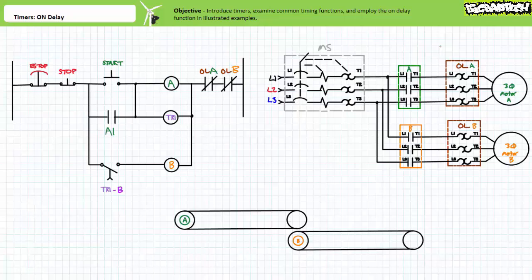That is that for this lecture. I was going to dive into on-delay timers coordinating reduced voltage starters; however, I'm going to hold that for another lecture since it comes with associated baggage — notably an understanding of reduced voltage starters. As a preview: the most basic application of on-delay timers is for scenarios in which one or more contacts must open or close a measurable time period after an input has been asserted. Primary resistor, part winding, and Y-start delta-run reduced voltage starters are all characterized by two distinct stages — start and run — and necessitate a reconfiguration during the transition. Some solid-state soft starters, specifically those that are AC53B rated, must be bypassed during the run stage and given a chance to cool. All these applications are perfectly suited for on-delay timers.